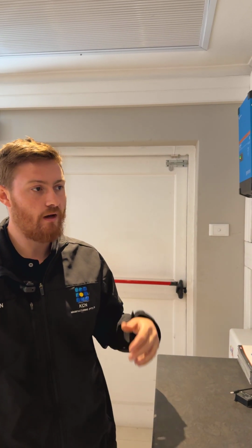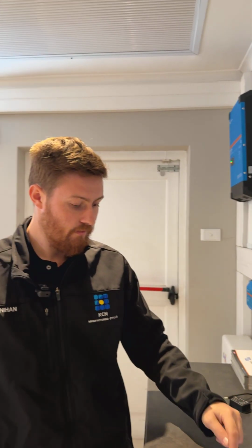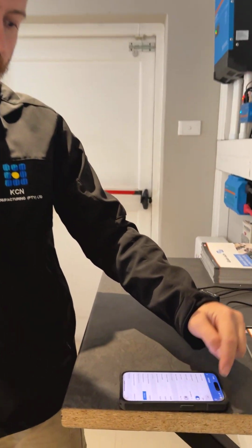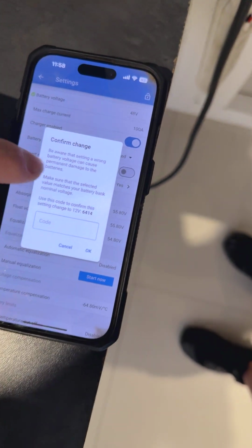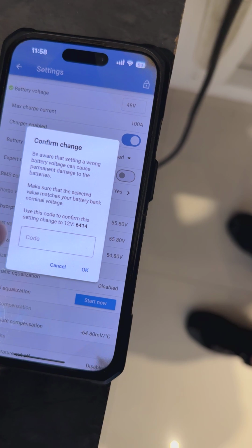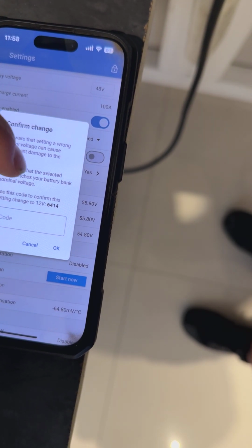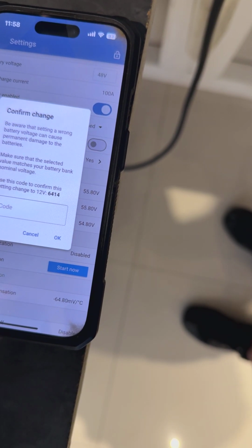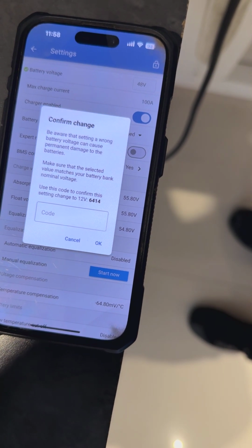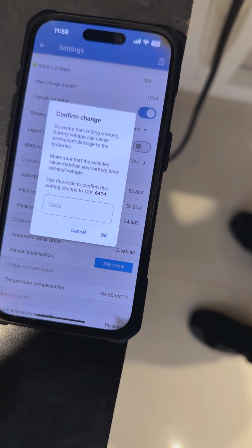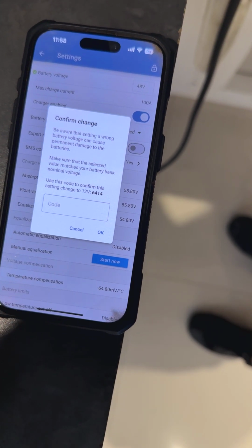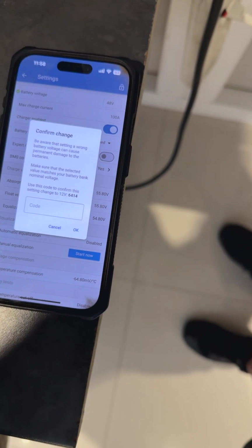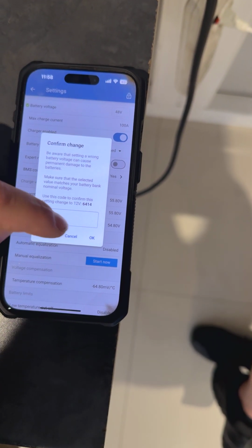So as general practice, I now always do updates on the PV side. On the latest firmware, the first setup actually blocks you from changing anything incorrectly - if I try to change it to 12 volt while 48 volts is connected, it asks for a PIN code and warns you to make sure the selected value matches your battery bank's nominal voltage. It's great that Victron added this feature to prevent over-voltaging a product set on a lower nominal voltage range.